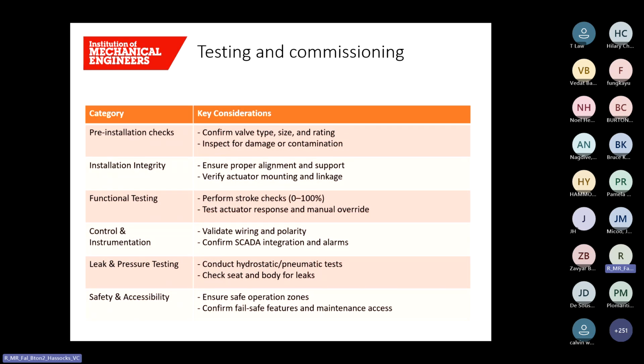You've got your pre-installation checks, where you confirm valve type, size and rating. It's also worth inspecting for any damage or contamination. Installation integrity: ensure proper alignment and support. Verify actuator mounting and linkage. Functional testing: perform stroke checks, 0 to 100%. Test actuator response and manual override.